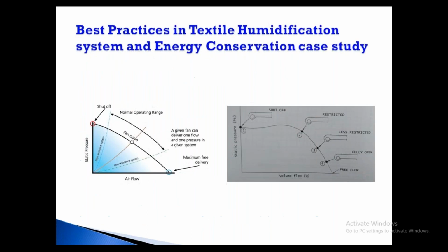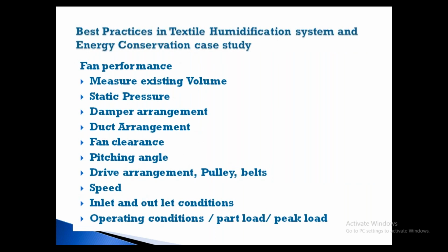So inlet and outlet condition, as I told, the bell mouth smooth curvature. You have a fixed cone, and the outlet also has a cone, so it will improve the performance of the flow. And what is the operating condition? It is very necessary to find out the fan operating condition. What is the part load? What is the peak load? Maximum peak load at a particular RPM and full plant when it is working. What are the conditions during that time? That data we have to collect, real-time data. Whatever I'm telling is all real-time data.